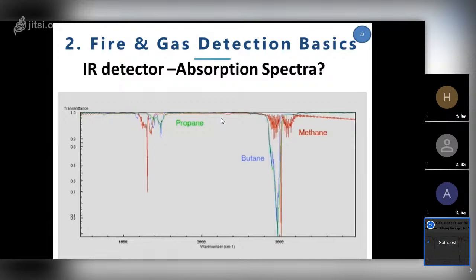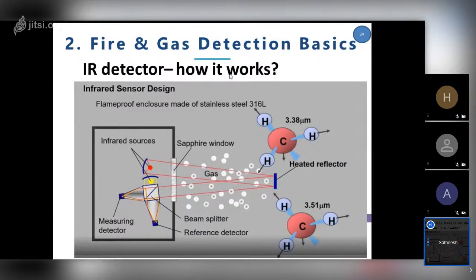Visible spectrum is what we see. Infrared spectrum is something different, away from the visible spectrum, and infrared is a light itself. You can imagine a light beam; when a hydrocarbon gas passes through this light, there will be an absorption. This absorption will be different for different hydrocarbons. You can see here, for example, the absorption peaks are different for butane and methane. So we use a gas detector with specific wavelength targeting, for example, propane. Then it will be sensitive only to the propane absorption curves. So when the gas comes into the path, there will be an absorption. We are able to catch this in the electronics and generate a signal proportional to the gas detected. This is quite complex to understand, but I'll make it very simple. This is the typical design of the infrared gas detector.